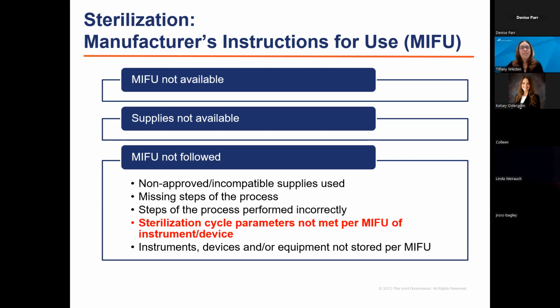So if there's a difference between the instrument or device and the sterilizer or sterilization accessory in use, and you want to find out which one is the correct one, you need to contact the manufacturer of the instrument or device and the sterilizer or accessory and get their response in writing, right? The manufacturers of the instruments or devices are required by the FDA to validate that the sterilization cycle parameters included in their instructions for use will yield an instrument or device that is sterile. So that is your baseline, right? You need to meet the manufacturer's instructions for use for the instrument or device being sterilized.